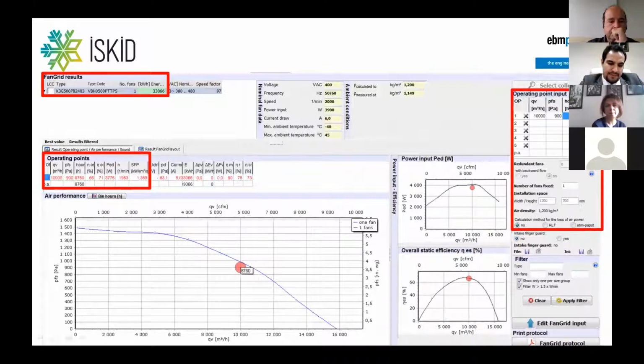And just to make it comparable, I put here in the annual 8,760 hours. And this will result in this fan, diameter 500, in an energy consumption of 33,066 kilowatt hours over the year. And you see we are quite close to the peak efficiency. And this is how we display that. And as mentioned, the losses can be considered. Like here, it's a calculation method for the loss of air power. It's not considered in this value, in this 33,000 kilowatt hours. And I want to show you now how this will happen if we use the RLT way. This is the way I explained before, or to use the EBMPAPST reduction of losses that we found out due to measurements.